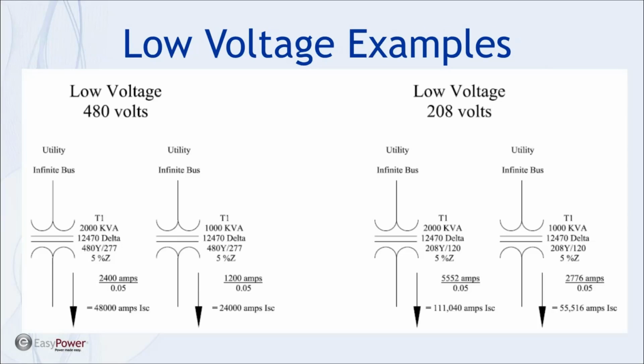So first thing I started with was just a couple of, you take a look across the board here, got two examples of transformers, two with a low voltage of 480 volts, two with a low voltage of 208, a 2000 and a 1000 kVA. And if we look here at the 2000 kVA with 5% impedance, I'm going to go over these calculations, but here's just the quick results. If we have a transformer that's got 2000 kVA that's got a percent impedance of 5%, that turns into 0.05 per unit. We take the rated current of that transformer divided by 0.05, we get 48,000 amps. So on a 2000 kVA transformer, that's the available symmetrical short circuit fault current.